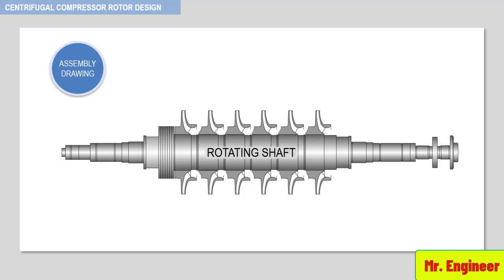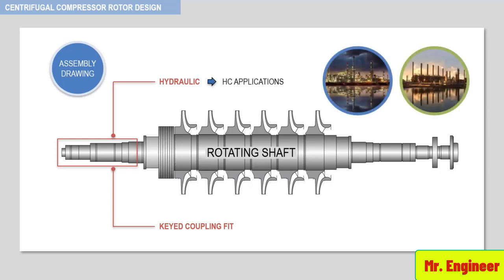Shaft ends can be designed either for hydraulic or keyed coupling fit. Hydraulic fits are usually used for compressors in hydrocarbon service, since the coupling must be removed to disassemble the shaft seal. And heat required to remove a keyed coupling would present a safety hazard. Coupling fits and mounting procedures will be discussed in the next section.